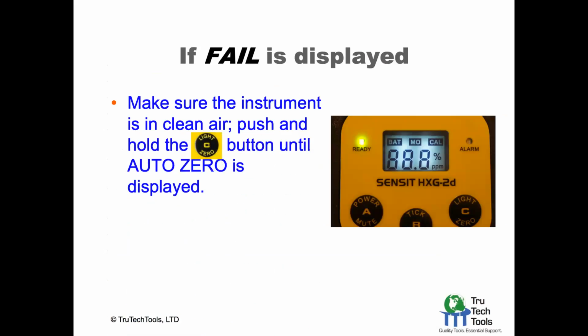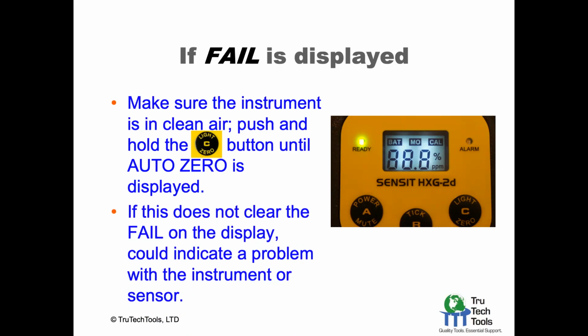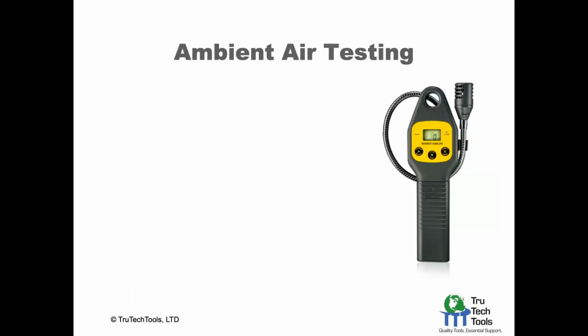If you ever see fail displayed on the screen, make sure to take the instrument to clean air, push and hold the 0 button until auto 0 is displayed, and then let it go through the zeroing process. If that doesn't clear the fail word on the display, that could indicate an instrument or more likely a sensor problem. And again, these are $45 sensors. But it is important to know, these sensors also have no shelf life. So if you want to be proactive and get some sensors in advance to have them on hand, they're just small little things, but they're very important. It's crucial to the operation of the product.